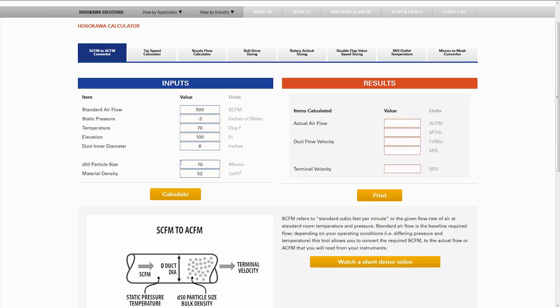Down here we also have a D50 particle size of the material in the air and a material density. You can run this without using the D50 or material density, or with it to determine the minimum velocity needed to carry the material in the pipe.